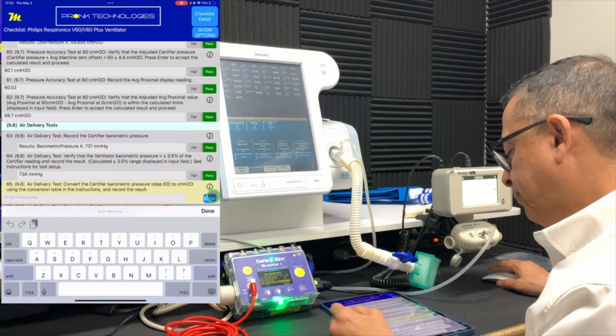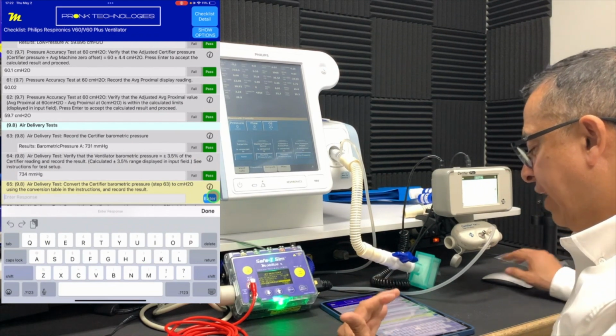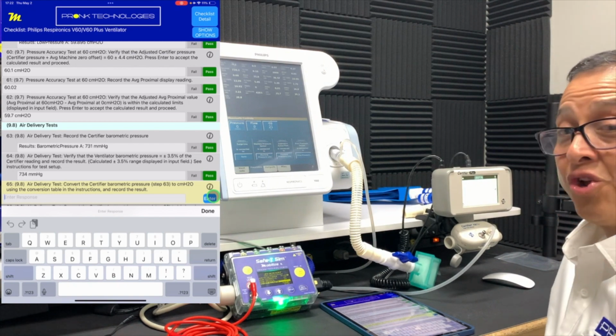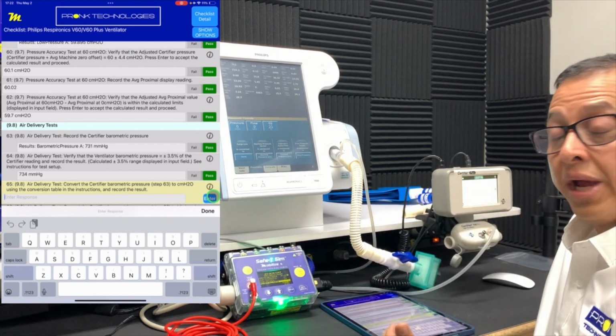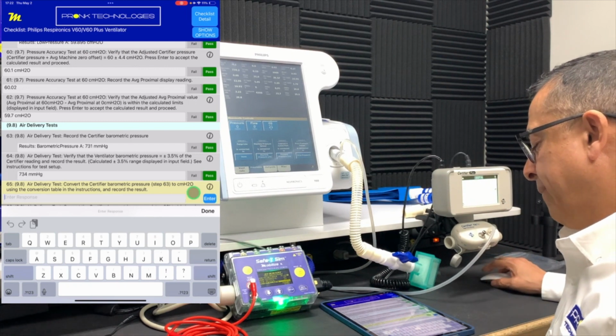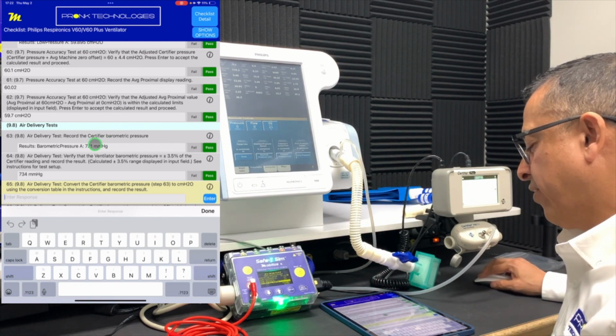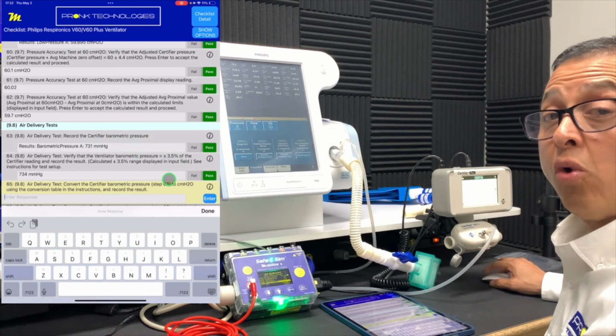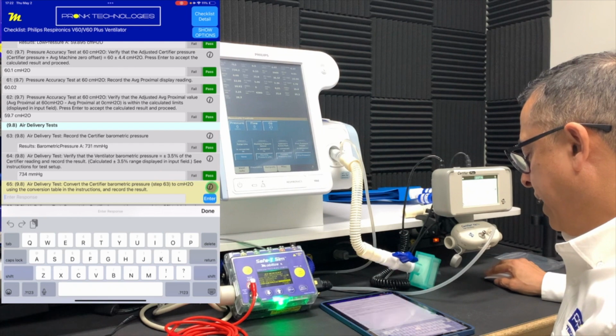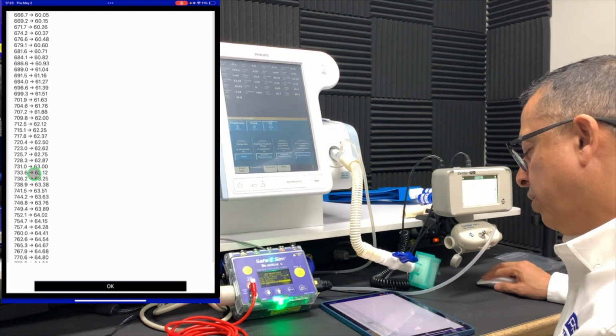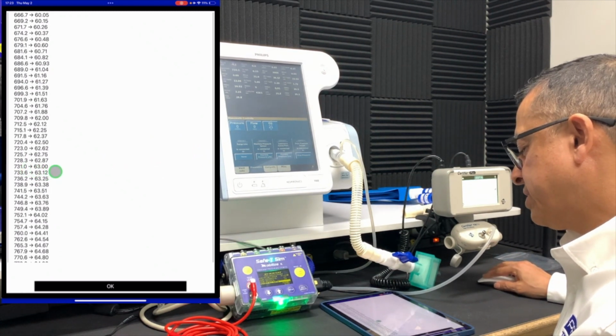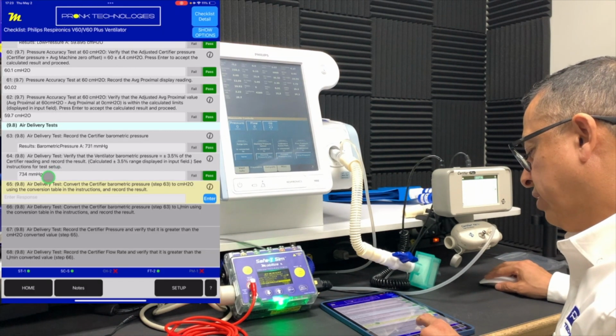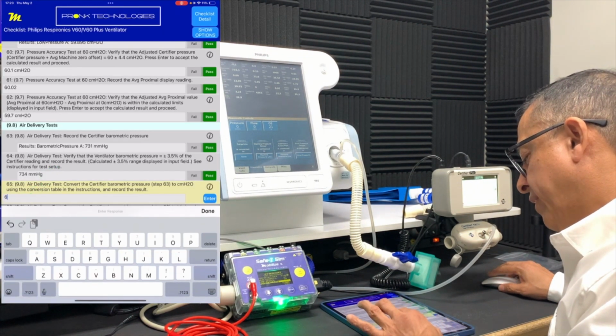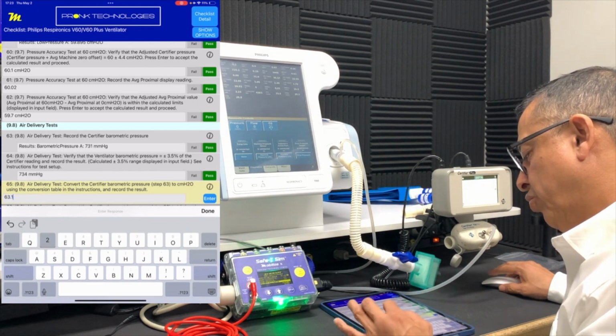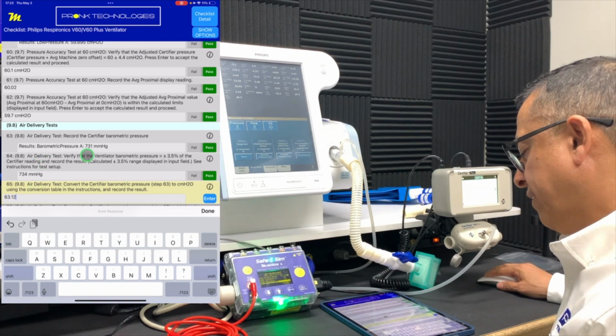And now we want to do an air delivery test by converting that barometric pressure to centimeters of water. So you have to do a conversion in order to get in the right units of measure. And so you need to convert that measurement we took in step 63, which was at 731 millimeters of mercury. We need to convert it to centimeters of water. Fortunately, within our procedure here, I can find that table and find that value. So we're looking for cert 734.1, which is right in this range here. So the value we want to select is 63.12. So I've looked that up and I want to enter in here that conversion value.